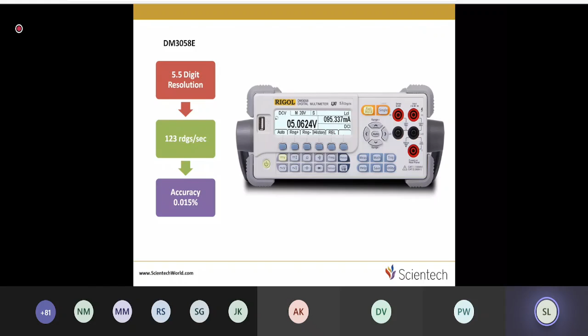If I go to another, 6.5 digit multimeter, the accuracy is 0.0035%. You can see that accuracy is improved, and for specific designs, 10K readings per second. Now you have to make a trade-off between resolution and speed. If I am a manufacturing company making sensors and I have to see the sensors' output, whether they are giving that particular voltage or not, then if the speed is slow, my productivity will be slow, because the measurement speed of that multimeter is very slow, although I am getting a high resolution.